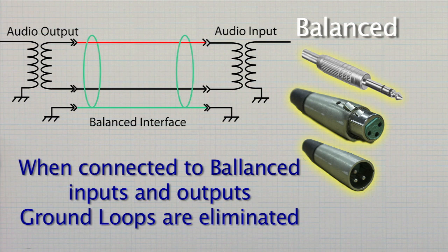Balanced circuits, on the other hand, eliminate this potential problem by keeping the second signal conductor separate from earth or chassis ground. Even if there is a ground potential difference, it does not affect the signal.